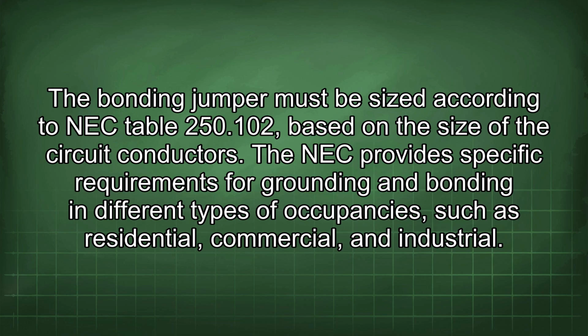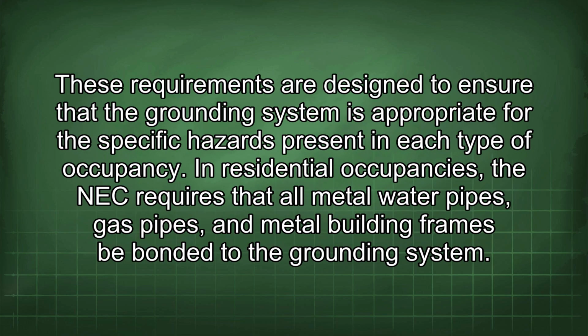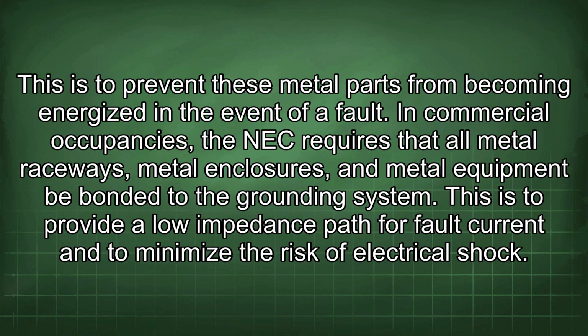The NEC provides specific requirements for grounding and bonding in different types of occupancies such as residential, commercial, and industrial. These requirements are designed to ensure that the grounding system is appropriate for the specific hazards present in each type of occupancy. In residential occupancies, the NEC requires that all metal water pipes, gas pipes, and metal building frames be bonded to the grounding system. This is to prevent these metal parts from becoming energized in the event of a fault.